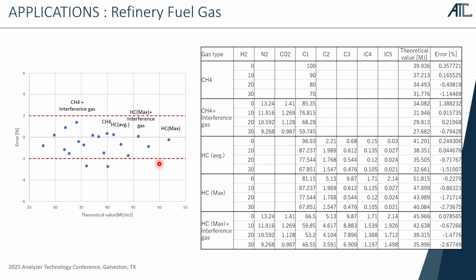And then most of the target gases are within 2% accuracy, except the gases with 30% hydrogen with the hydrocarbon rich gases. So this one shows 2.7%. This one shows 2.7% accuracy. But other than these two gases, the accuracy is quite high.